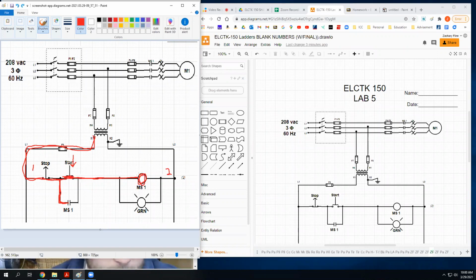This is energized. Just like a control relay, when this is energized, any normally open contacts that are on there are going to change state. This normally open contact down here is mounted right to the motor starter. So when this coil gets energized, this closes. And because all of this is parallel, it allows current to flow here too. Right? Yep. So now that I have current flowing in this path as well, it's also going through here because this is parallel. But now the important part is right now I have current flowing through here, and all I did was press that start button.